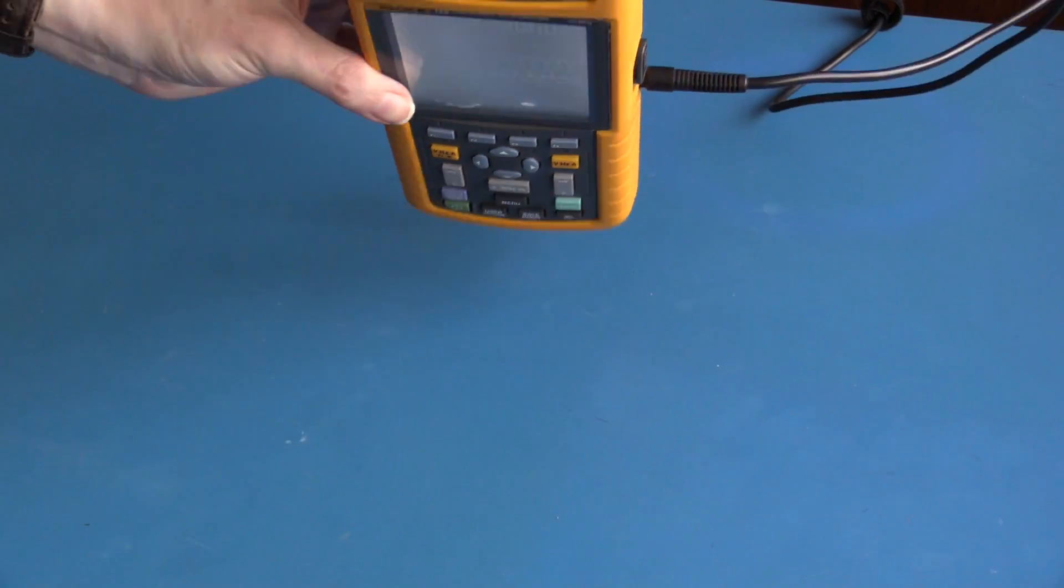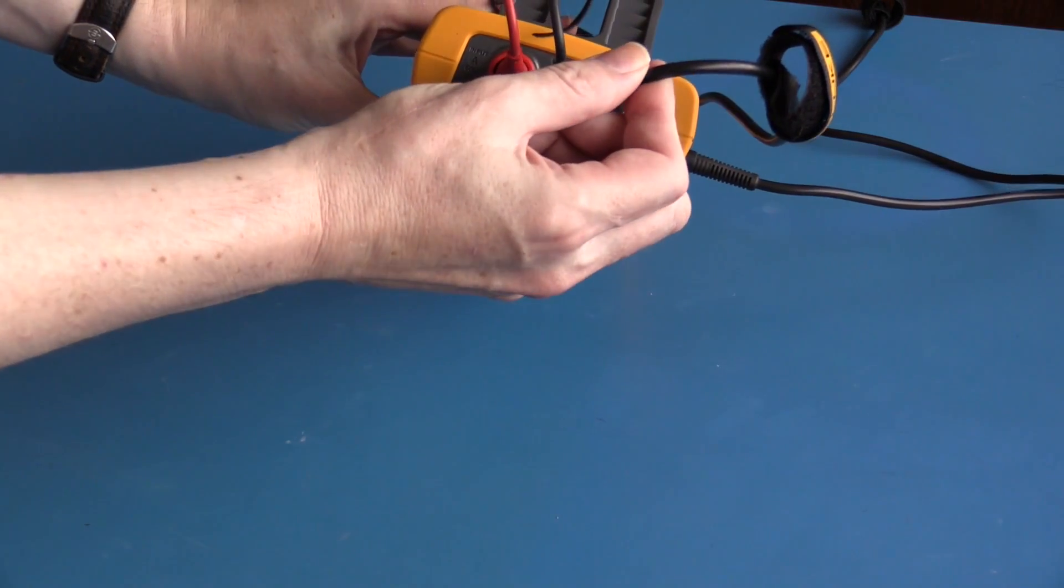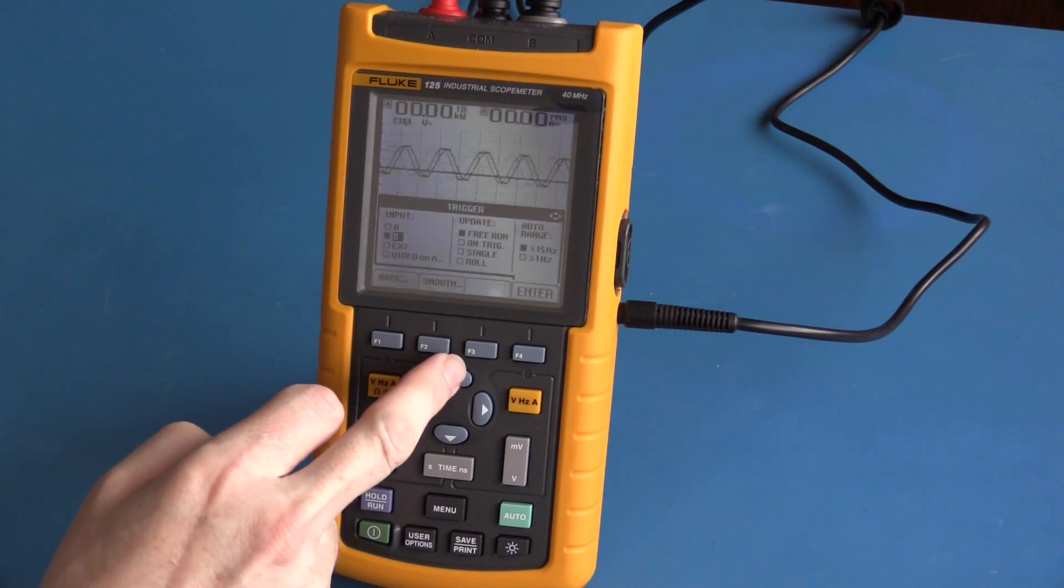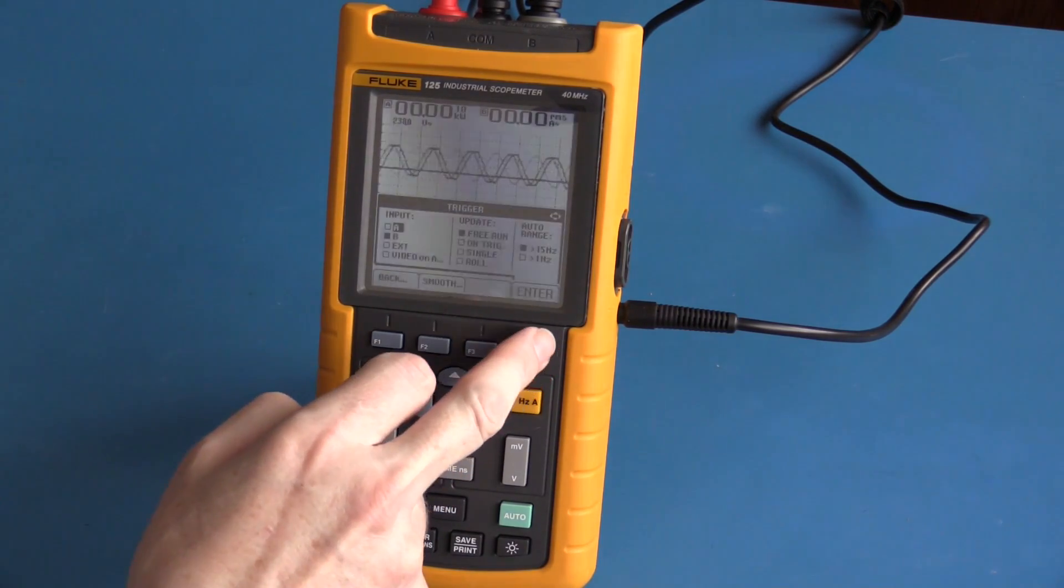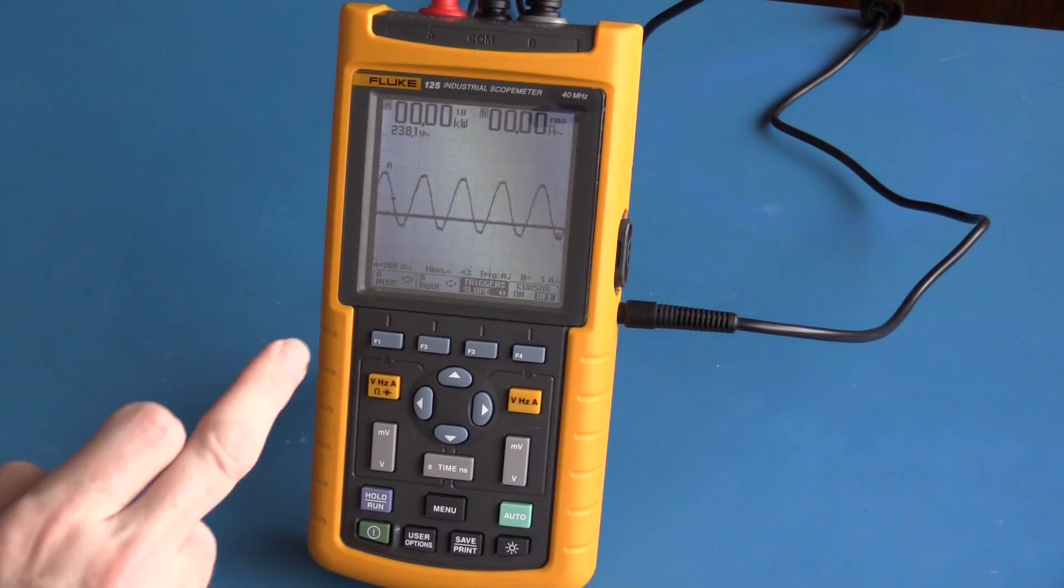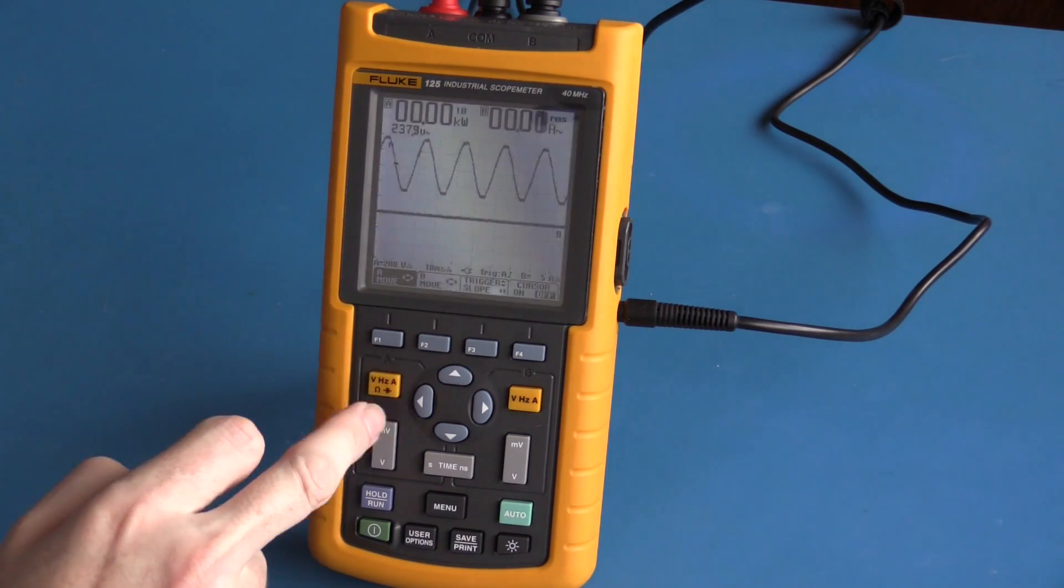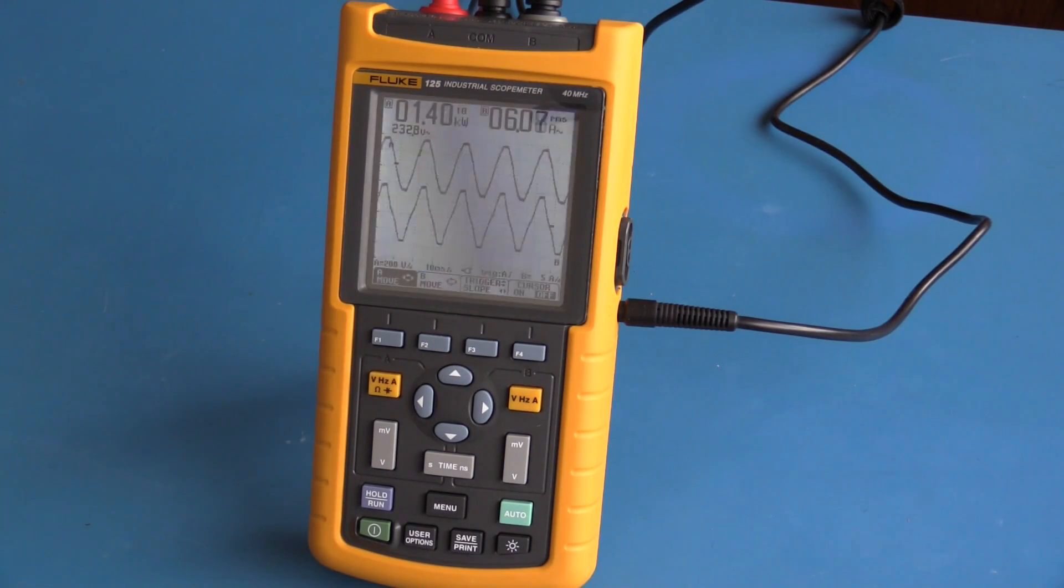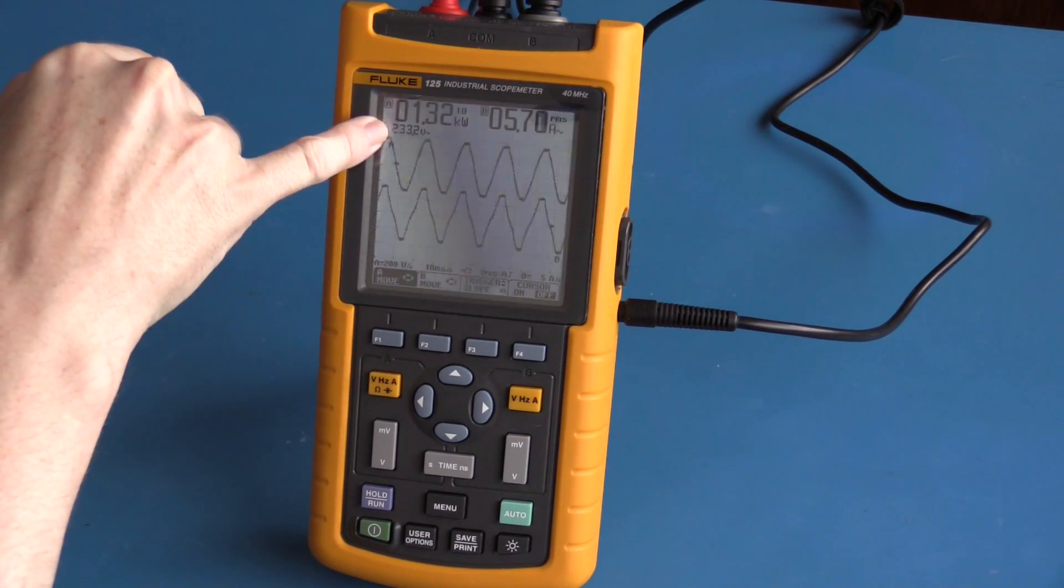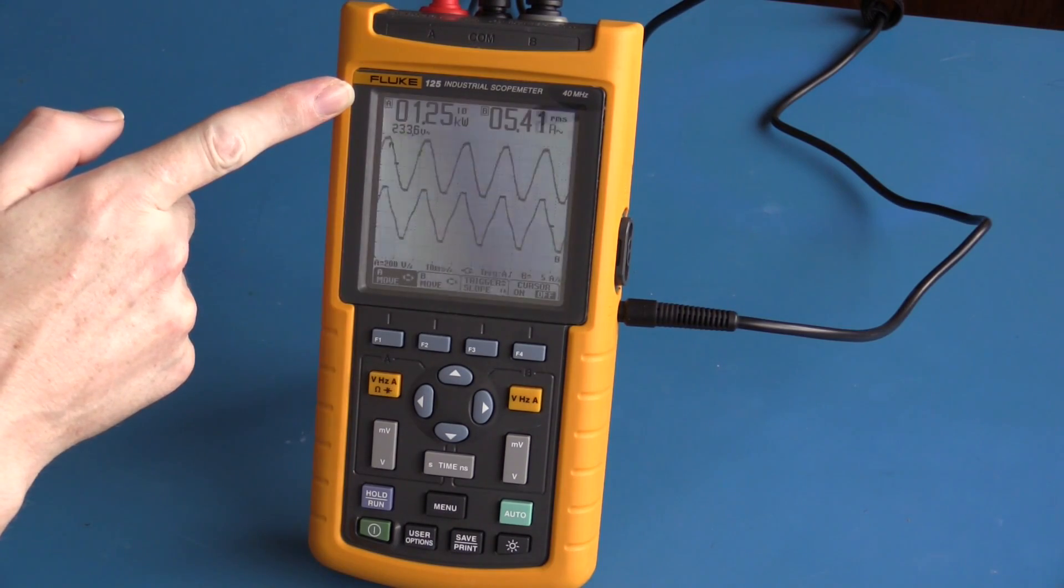To take a power measurement I'm now using all three inputs, voltage and my current clamp. I will trigger on channel A. I will then move the waveform channel A up. I can now see on my screen both the voltage waveform and the current waveform. 203 volts, 5.5 amps, and approximately 1.2 kilowatts.